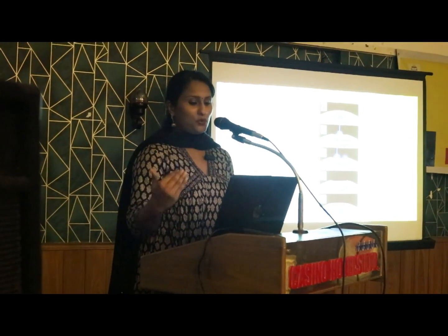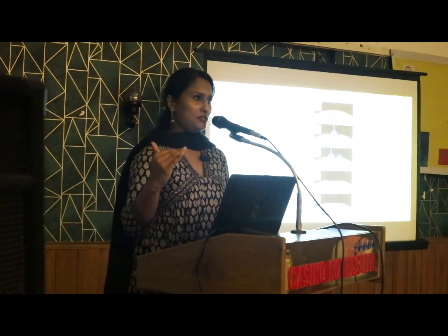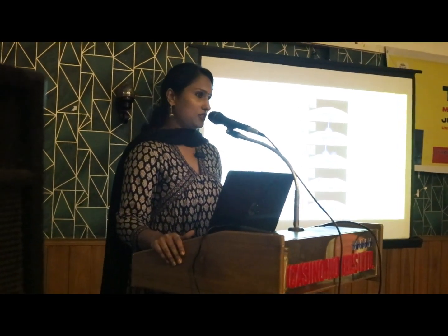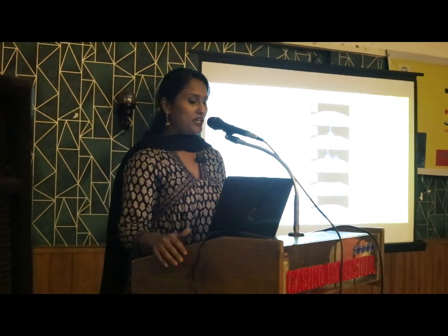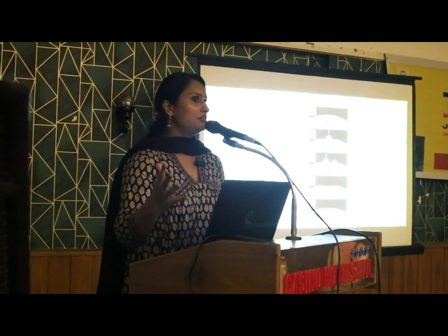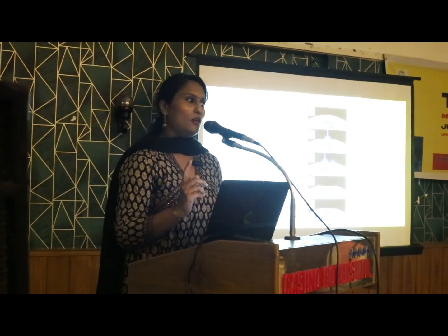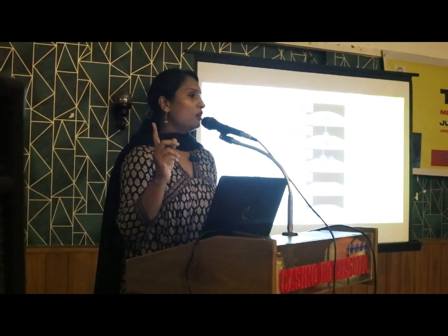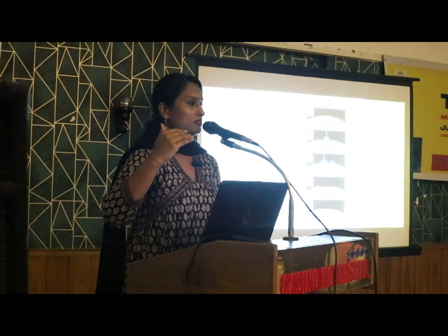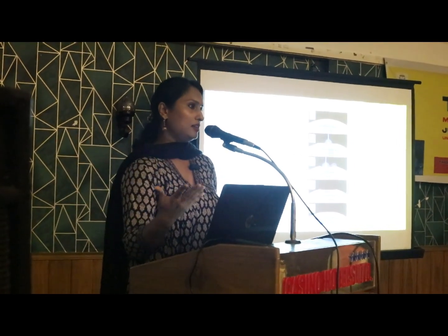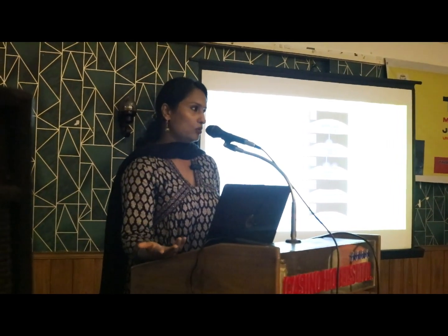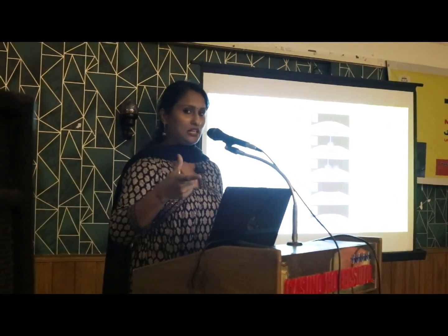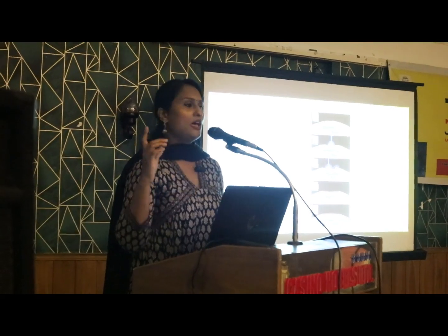So in summary, the procedure happens like this: first there is laser refractive stromal ablation, which is immediately followed by epithelial ablation. So what is the difference from the earlier forms? As I already said, in the earlier machines, the first ablation is of the epithelium, of around 8 mm. Then you have to manually switch the laser to a PRK mode, where the stromal or refractive ablation happens. So there is a time delay between the epithelial ablation and the stromal ablation.